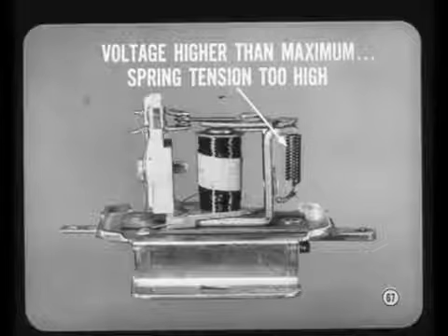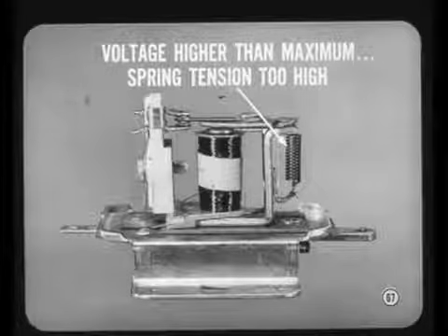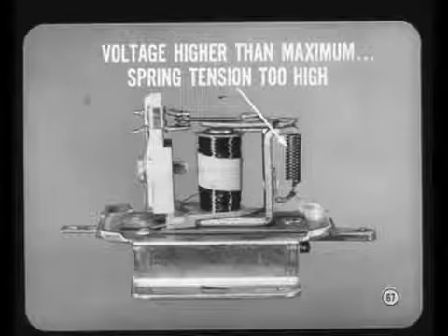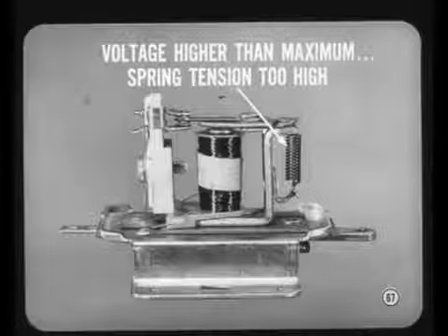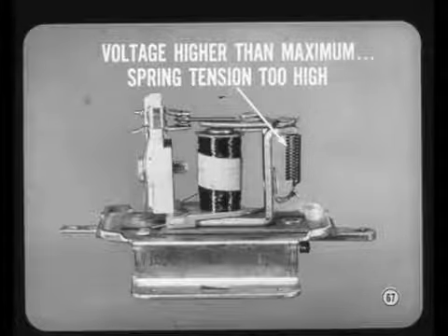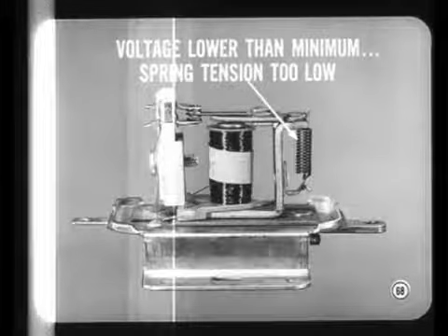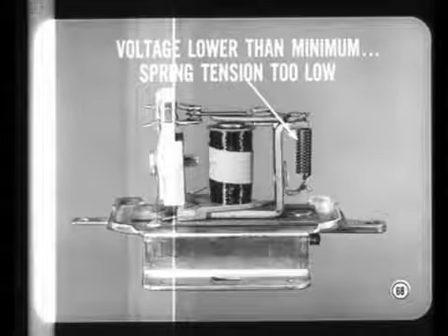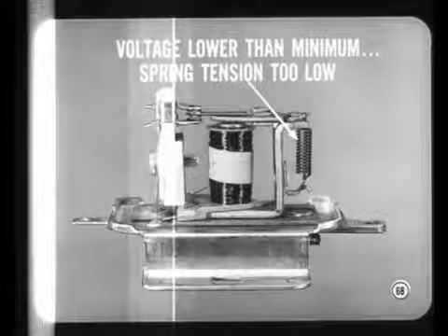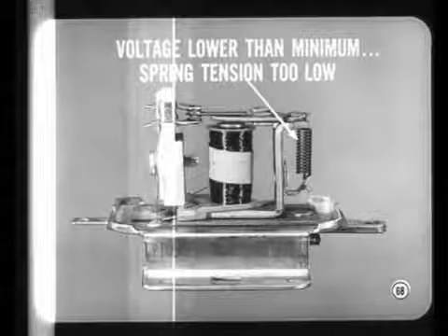If you find that the voltage is higher than the maximum spec, armature spring tension is probably too high. After adjustment, be sure to replace the cover and cycle the regulator before retesting. When you find the voltage below the minimum specification, armature spring tension is most likely too low.